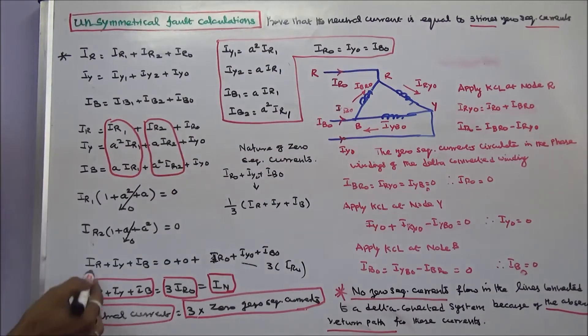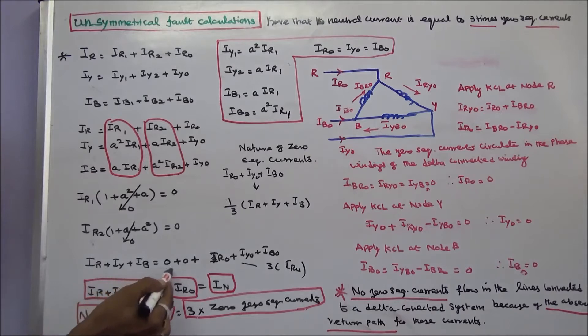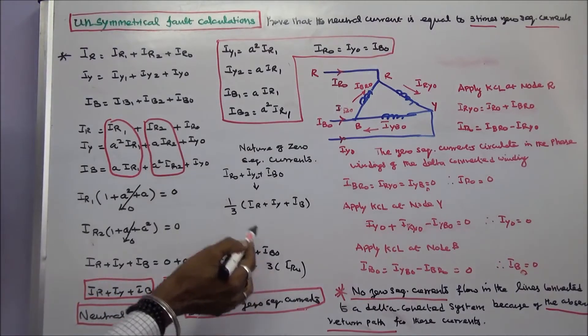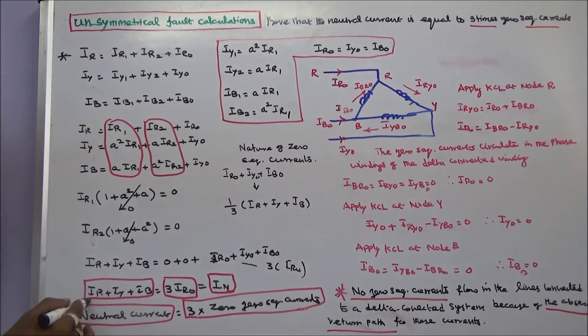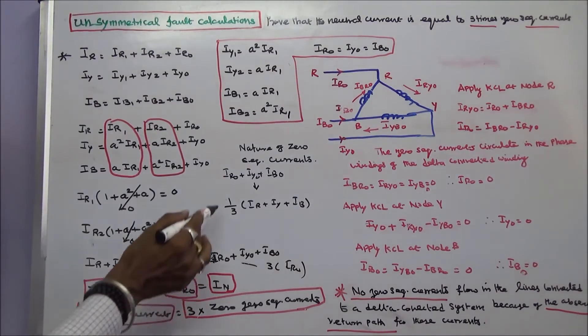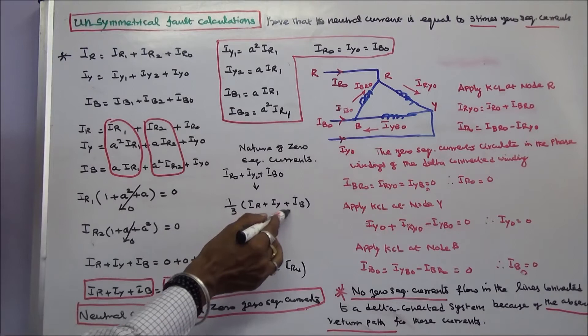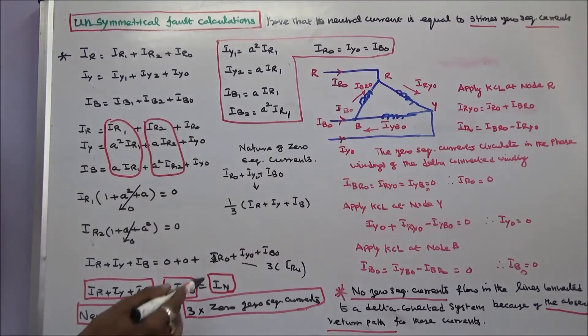Substituting these values, IR plus IY plus IB is equal to IR0 plus IY0 plus IB0. Since IR0 equals IY0 equals IB0, therefore IR plus IY plus IB is equal to 3 times IR0 — that is the neutral current. The zero-sequence current IR0 is equal to one-third times (IR plus IY plus IB), and the neutral current is equal to 3 times the zero-sequence current.